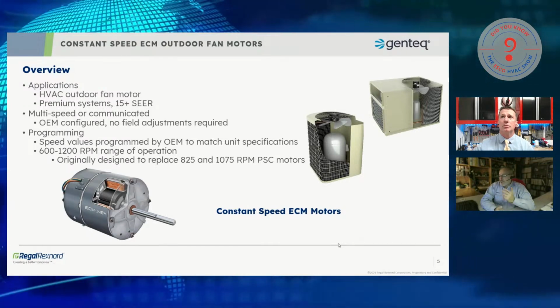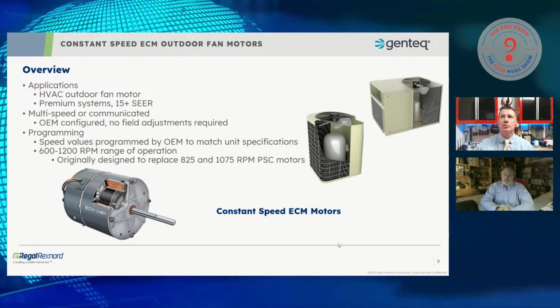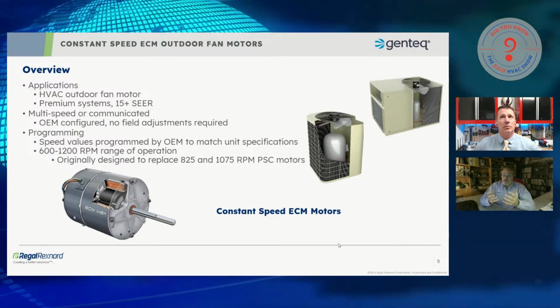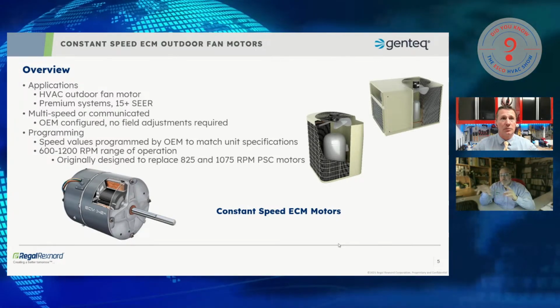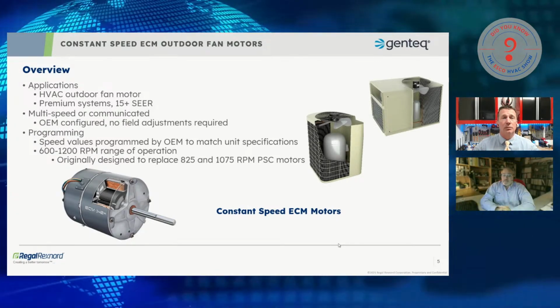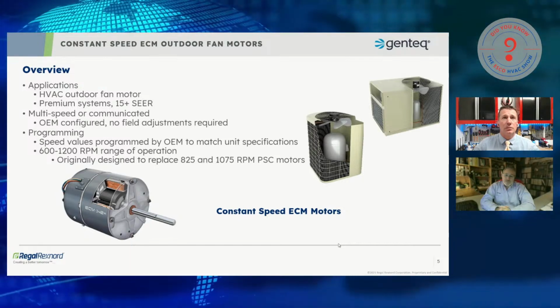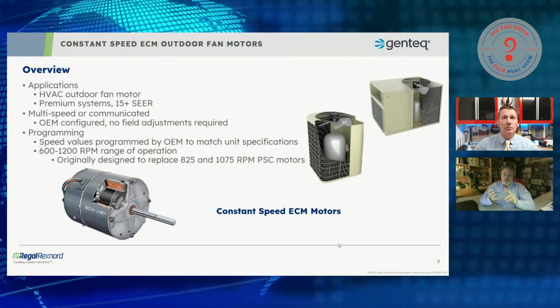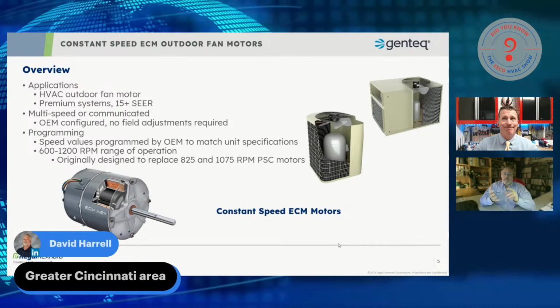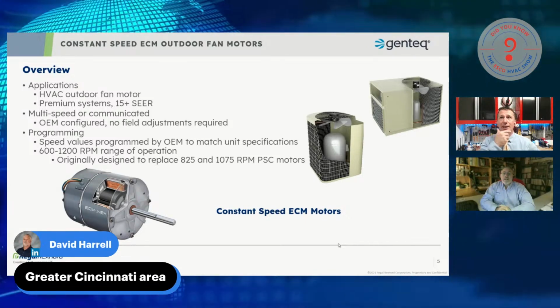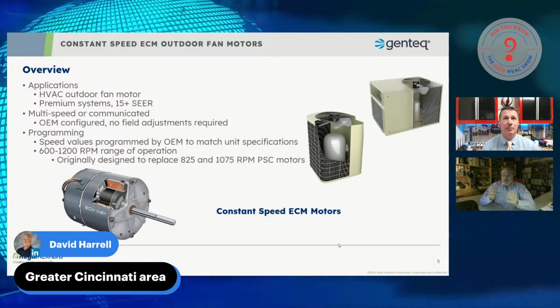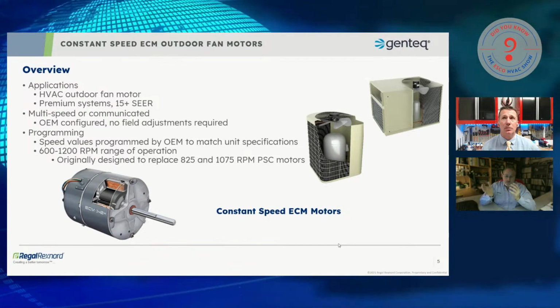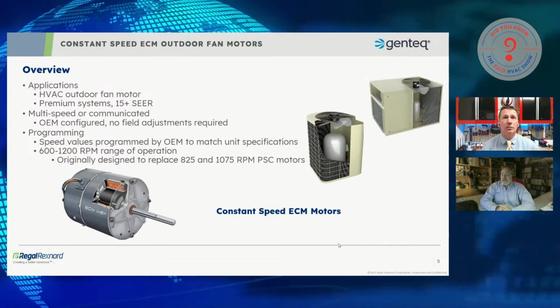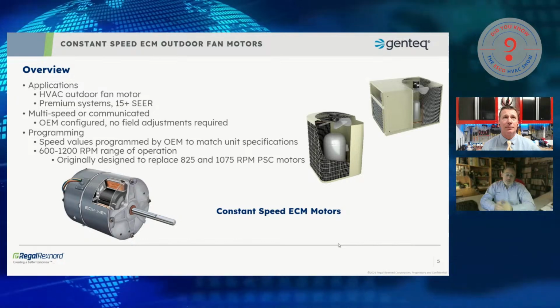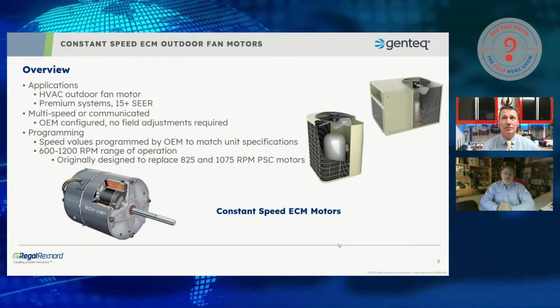So these motors do have a 600 to 1200 RPM range. In other words, the way we build them, they're capable of operating between 600 and 1200 RPMs, and that's because they were originally designed to replace the 6-pole 1075 and the 8-pole 850 or 875 or 825 RPM PSC motors. So we designed the ECM to replace what was existing in the equipment at the time. And the OEM may program, when I say OEM, I mean the HVAC manufacturer.